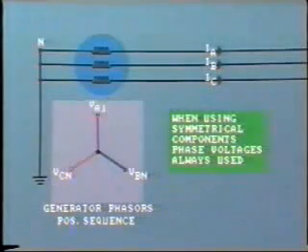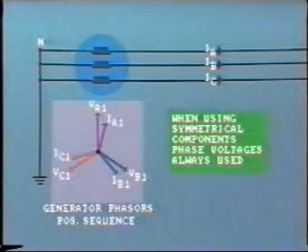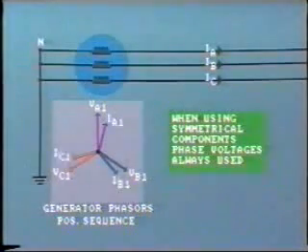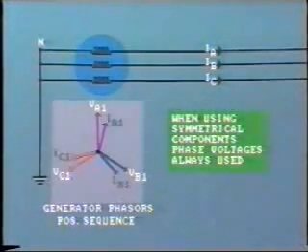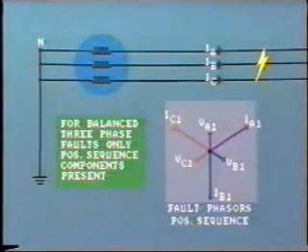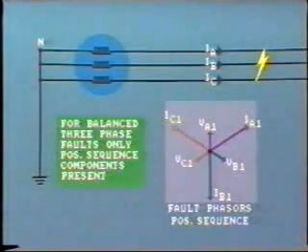For example, VA1, VB1, and VC1. With a balanced load, the current phasors produced by the generator are also similarly balanced. They'll look like this — once again, marked IA1, IB1, and IC1. For study of balanced faults, such as a three-phase short circuit or three-phase to ground, only these positive sequence components are needed.